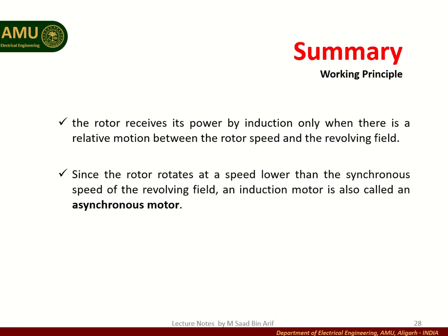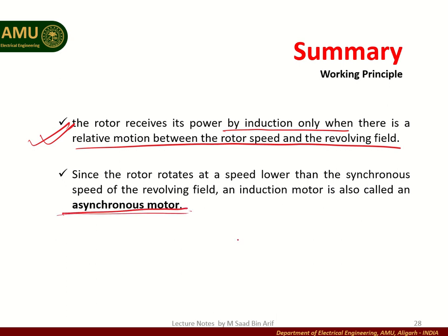Now look at a summary of this principle of operation. What we get from this discussion is that the rotor receives its power by induction only when there is a relative motion between the rotor and the revolving field. Since the rotor rotates at a speed lower than the synchronous speed of the revolving field, an induction motor is also called an asynchronous motor, as we specified earlier in this lecture. That's why we sometimes call it by that name also.